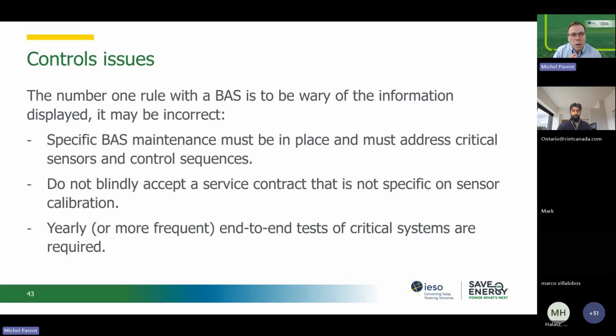The number of control issues that you can have in the building, just like the other issues we talked about today, is near infinity. There can be so many issues. So the first course of action is: don't trust all of what you see on the BAS. When you're in a room with the operator and maybe your EBCx provider, I always say the biggest liar in the room is the BAS. I never trust the BAS until I verify it. So how do you verify it? You will have to have a proper PM program just for the BAS. That usually takes the form of a service contract with whomever installed that BAS.